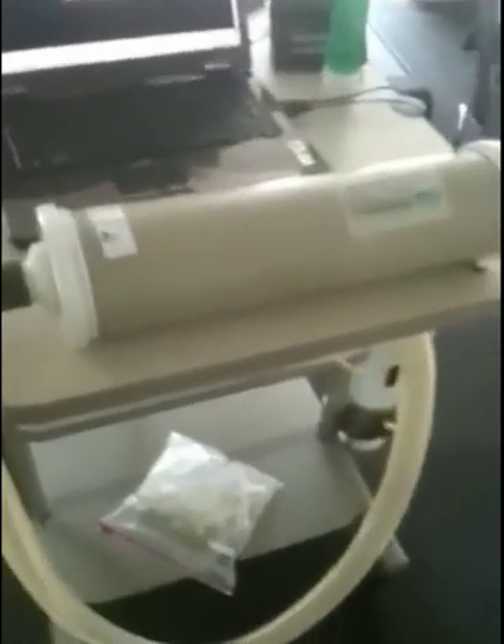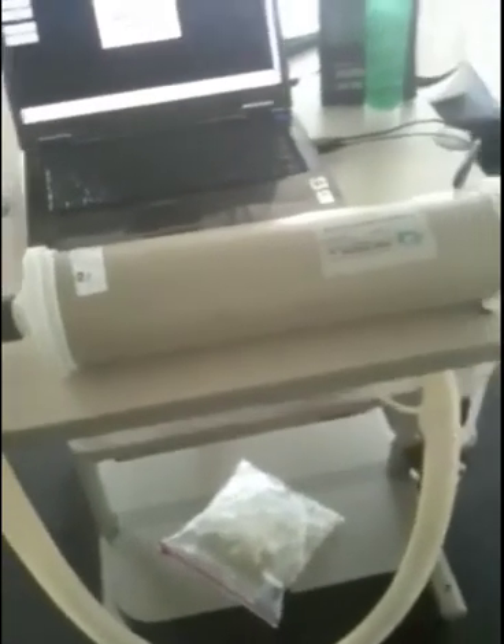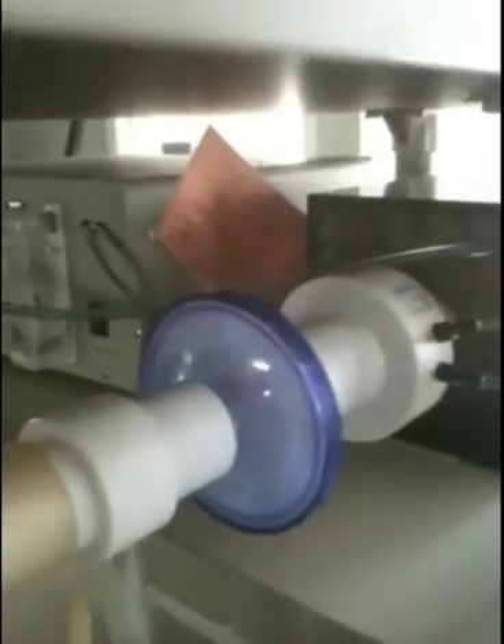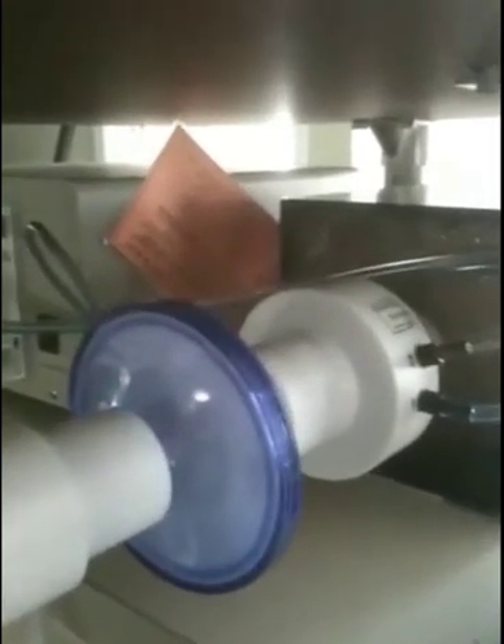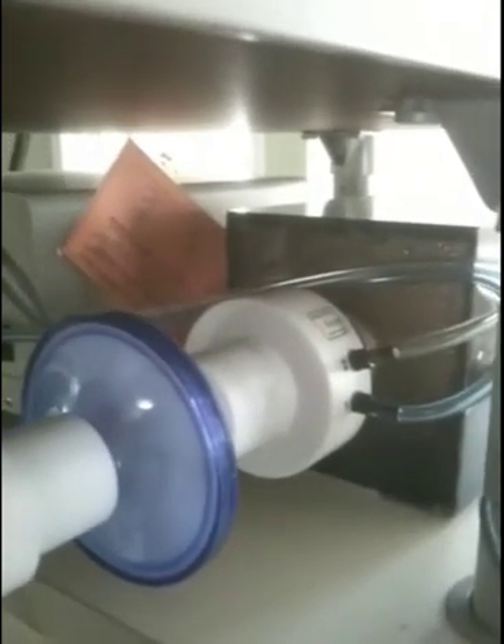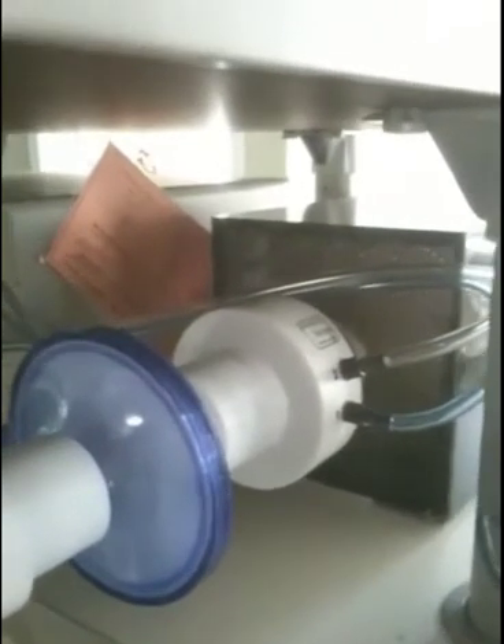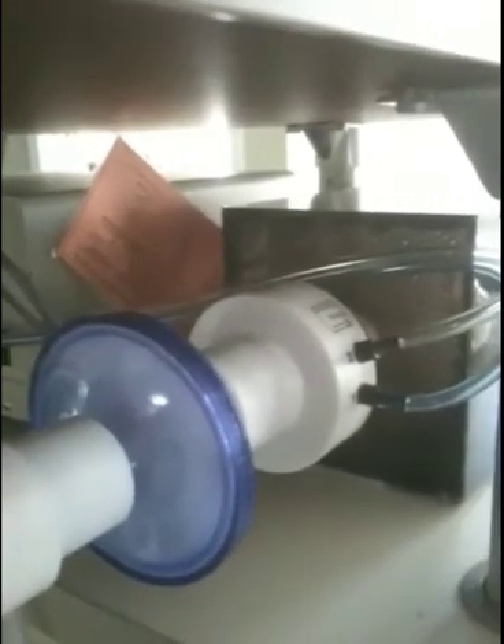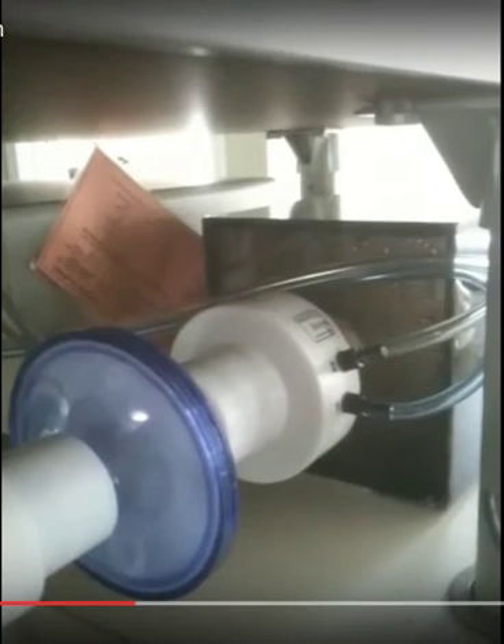So with each plunge of the syringe, it pumps in 3 liters of air, and that is used to calibrate the device down here that we see. The white component with the hoses coming out of it is called a flow meter, so that it precisely measures the amount of air that is passing through it.